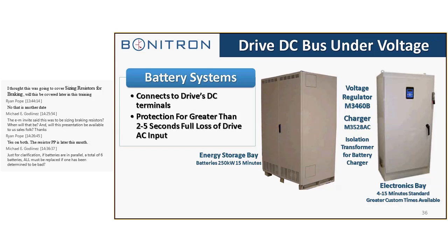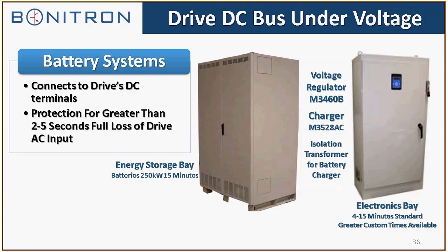Now this shows the cabinet system for the batteries. On the left is the energy storage bay. As I said, when you get up around 50 kilowatts, 60 horsepower, we have to start separating the energy storage from the electronics bay, just due to size. So the batteries will go in one cabinet, and the electronics will go in the other cabinet.